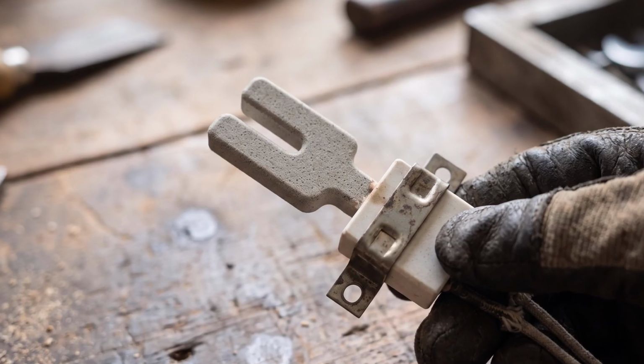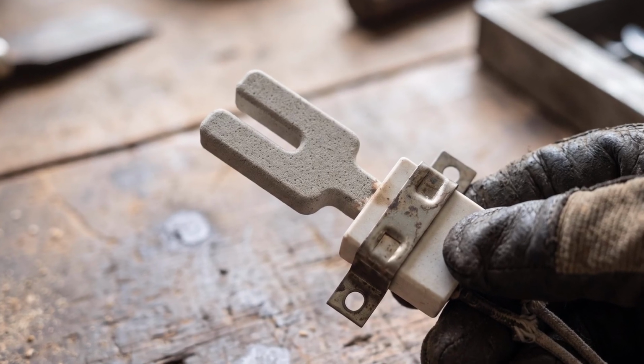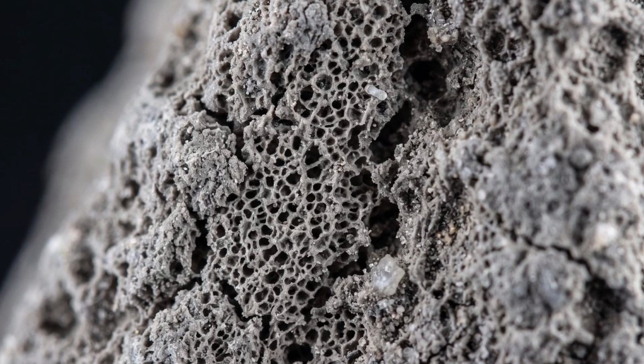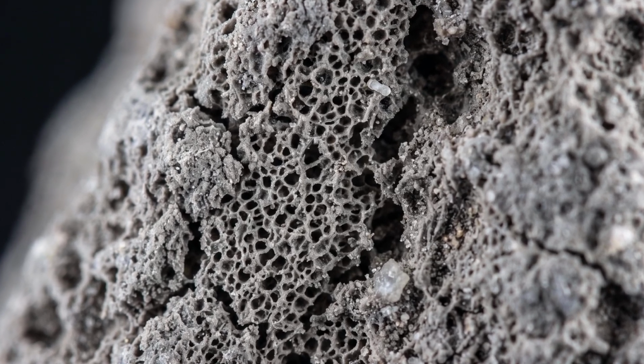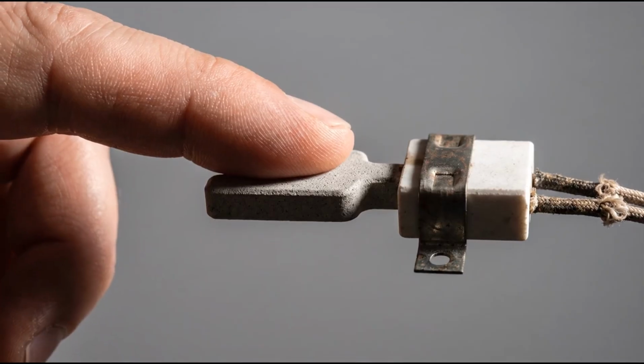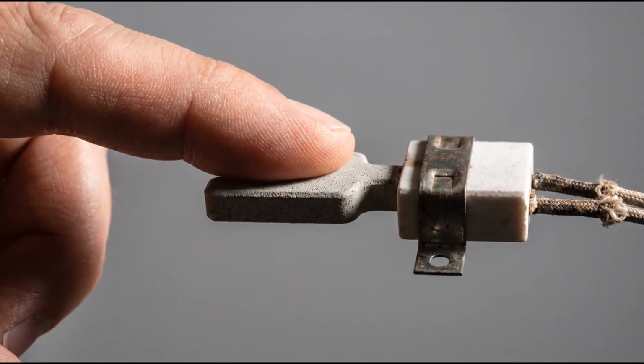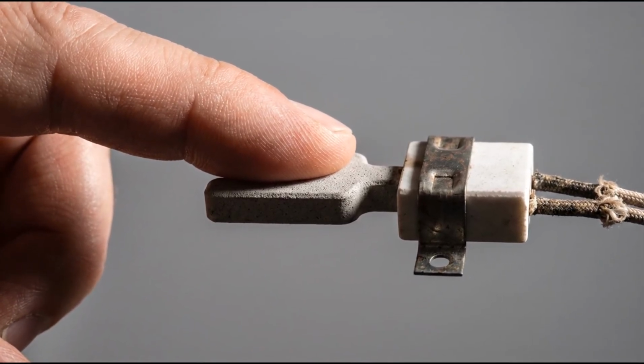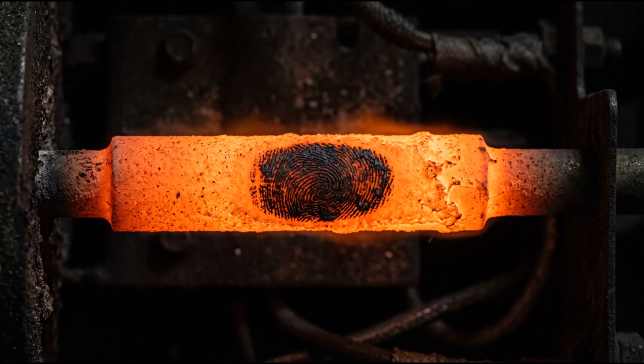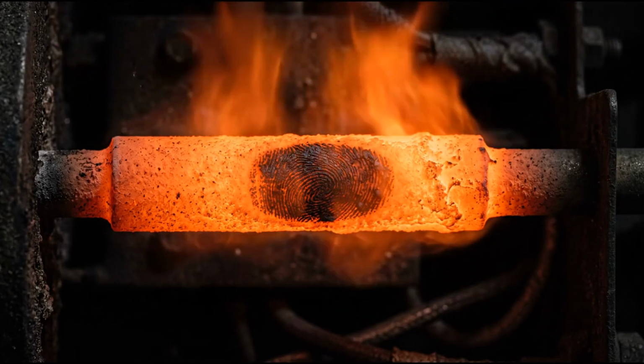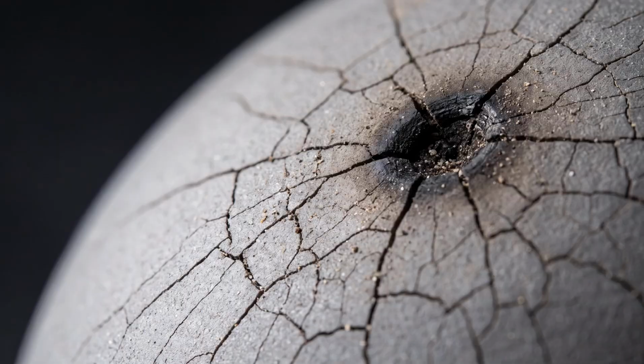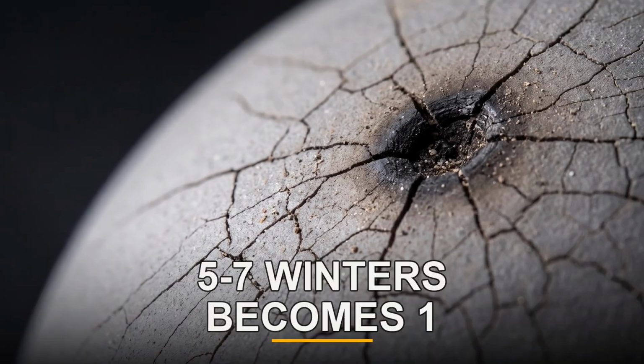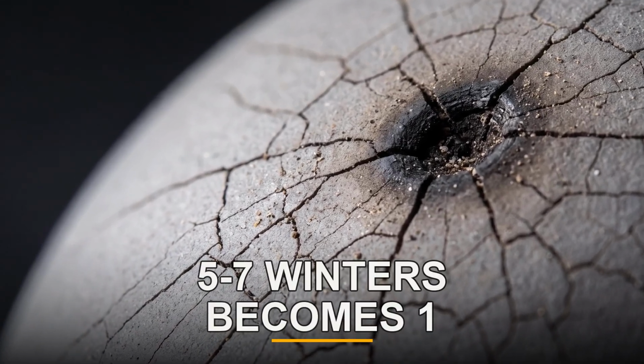The old flat-style igniter, silicon carbide, is porous ceramic. If you grab the element with your bare fingers, the oil from your skin soaks into it. Next time it heats to 1800 degrees, that oil burns, and it burns a weak spot right into the ceramic. The igniter that should have lasted 5 to 7 winters cracks in one.